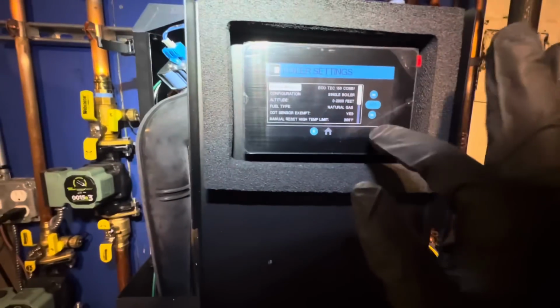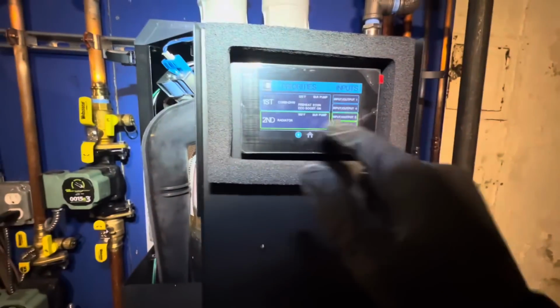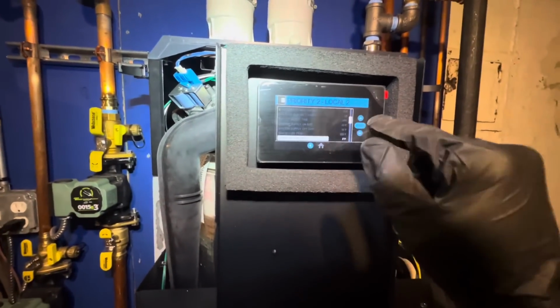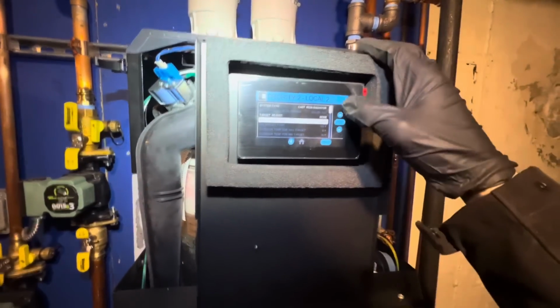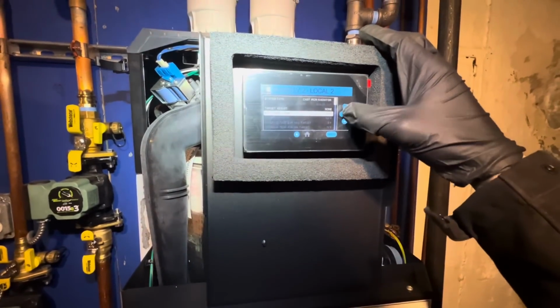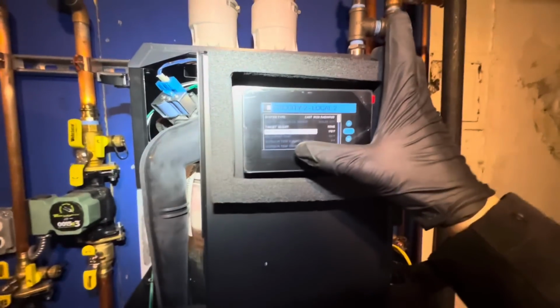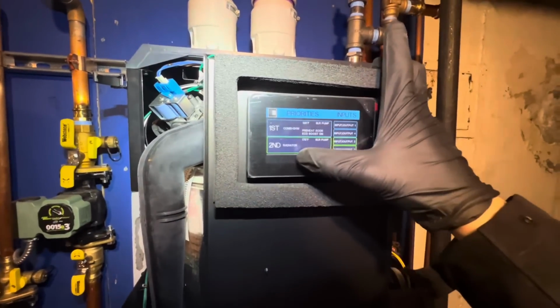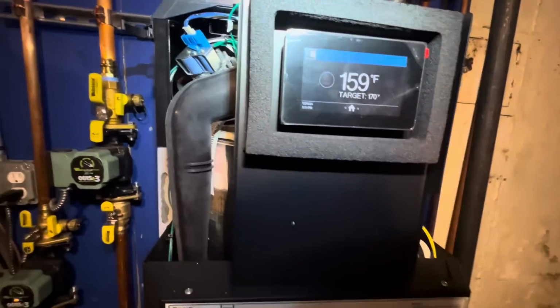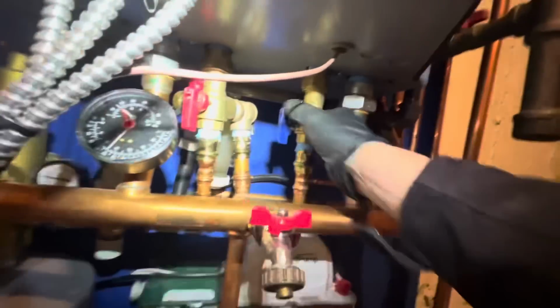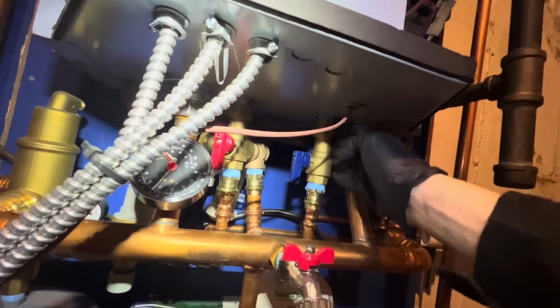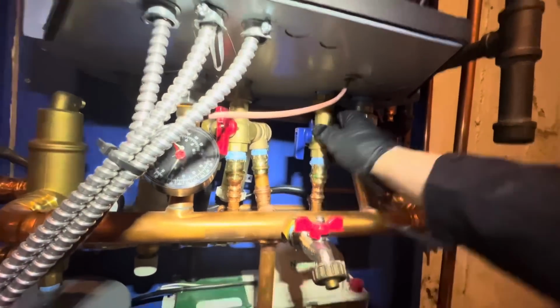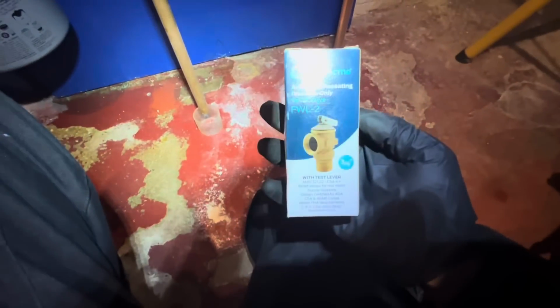So I'm going into boiler settings, and I'm gonna change the set point temperature for space heating up to 180, actually I'll go up to 170, because the customer did notice that the house was slower to heat up when it was really cold out, like it was noticeable. I put it at 160 for efficiency, but we want to make sure that the house can get nice and warm. This pressure relief valve, well, that's a new one now, but it was dripping. That was the pressure relief valve that came with the flush sets. So we put in the ones that we like to install, which is these.